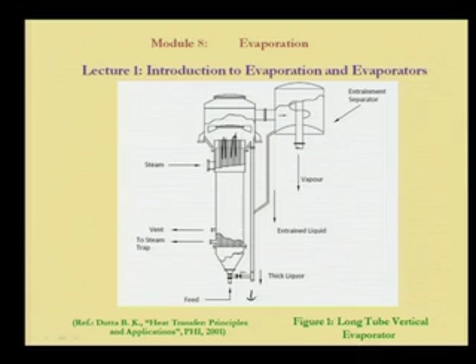And then the usual things: the LTV, long tube vertical evaporators, have tubes of 3 to 10 meter length and 1 to 2 inch diameter. Okay. The tube bundle diameter is less than in the STV, short tube vertical cases, and sometimes baffles are also used on the shell side to have more uniform flow of steam.